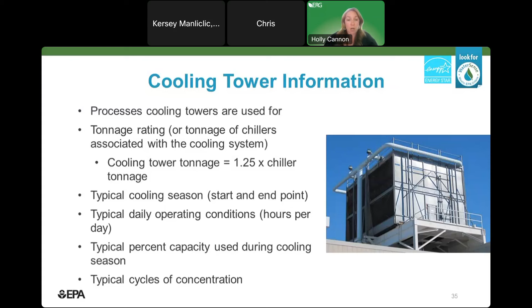You want to look at any submeters that are installed and tracked. They can commonly have a meter on the makeup and blowdown line, so try to obtain records from both of those if they're there. You'll also want to check the conductivity controller to see what conductivity the tower is operating at and compare that to the set point. Comparing those does help you understand the cycles of concentration. So the values should be on the conductivity controller, and the controller should have a set point, and they should be trying to maintain the conductivity right below that set point. If they don't have one, it's a great project to recommend that they get a conductivity controller installed.